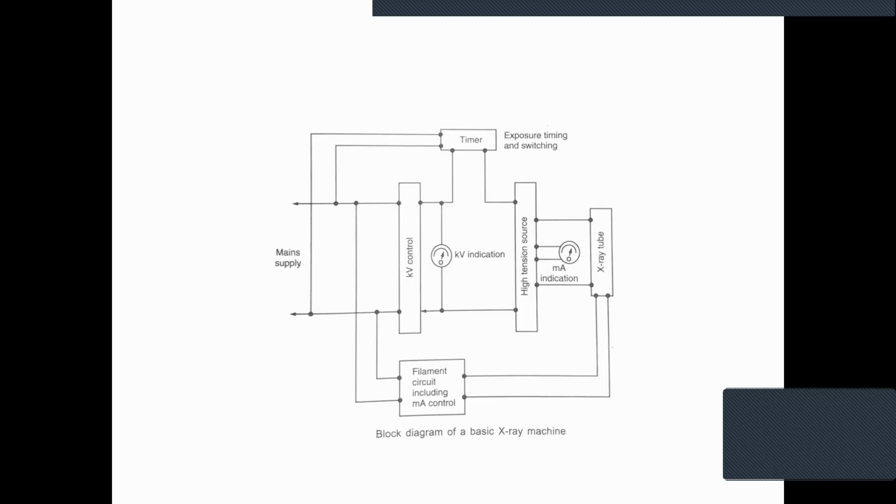In this block diagram, the diagnosis X-ray machine has a high milliampere, large current for heating the element, and a low exposure time. For therapeutic purposes, the X-ray machine has very low milliampere and high voltage potentials.